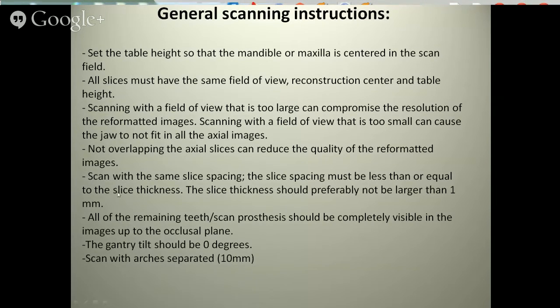A big one here is scanning with the same slice spacing. Slice spacing must be less than or equal to slice thickness. The slice thickness should preferably be not larger than 1 millimeter. If we go larger than 1 millimeter, the scan tends to get distorted, and we can have the same issue with pixelation. So when you're in your machine, make sure you have between 0.5 and 1 millimeter of slice thickness for accurate planning.